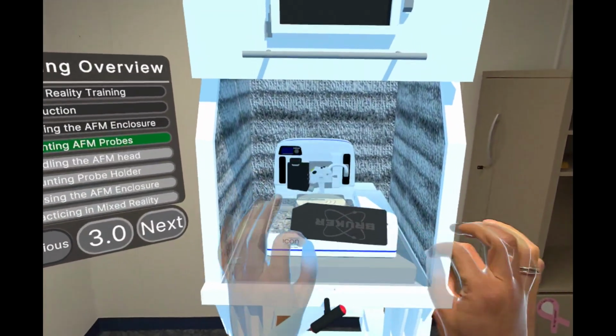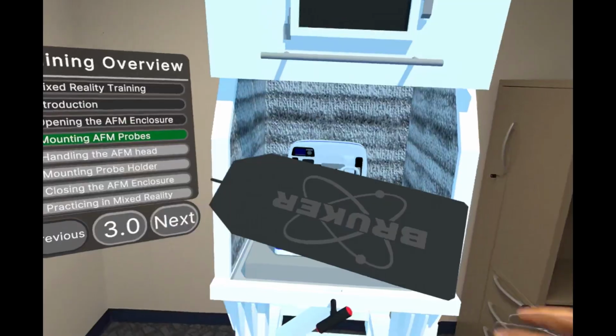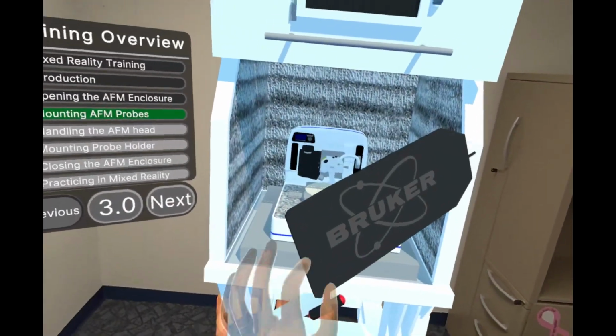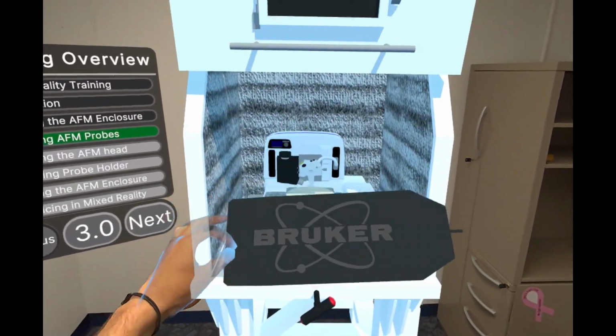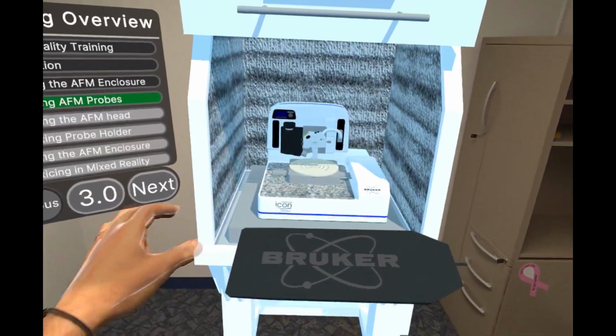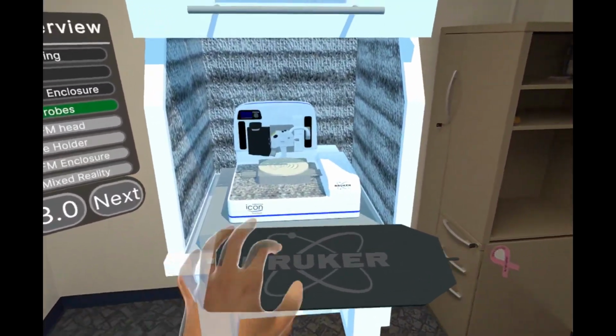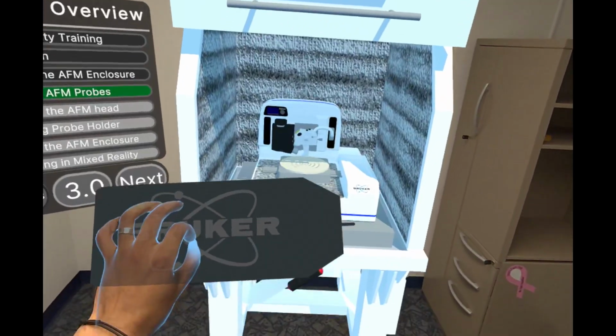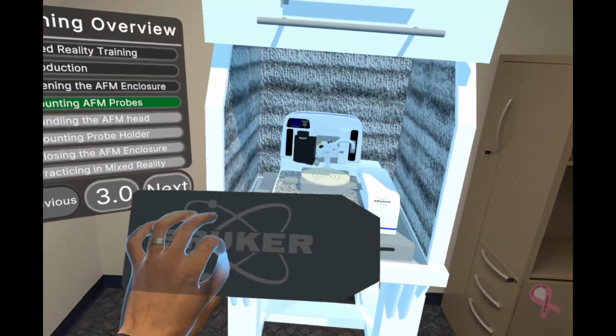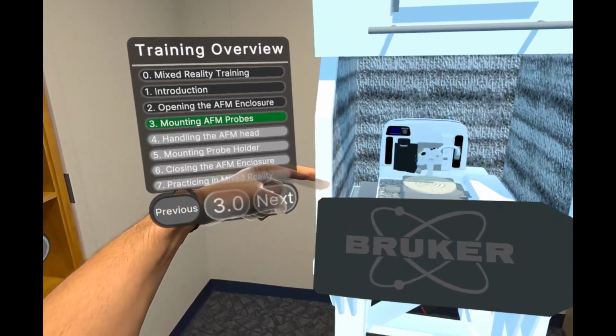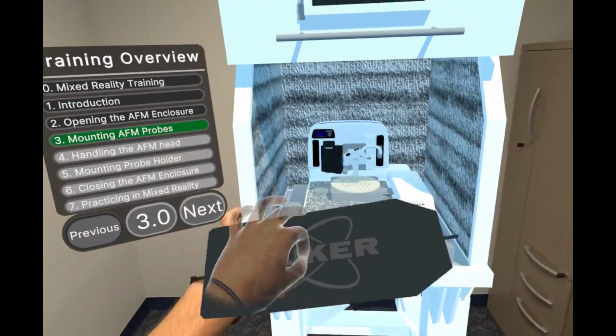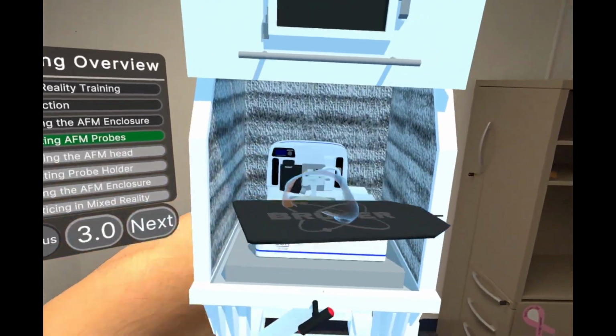It is important to understand the probe geometry so you can identify the correct orientation for mounting the probes in the probe holder. The front side with the cantilever has 3 angled edges, while the back has just 2 rectangular 90-degree corners. The back side will sit in the bottom of the probe holder channel when mounted correctly.